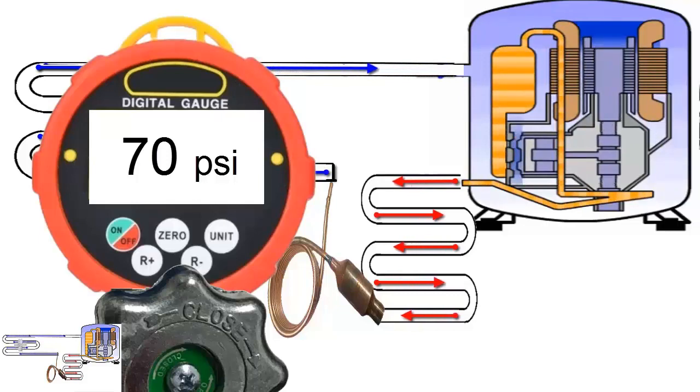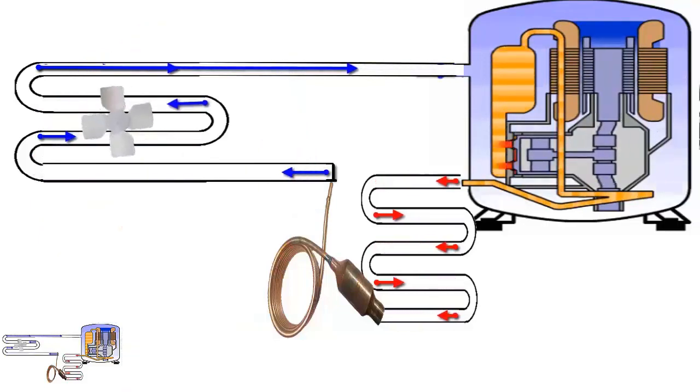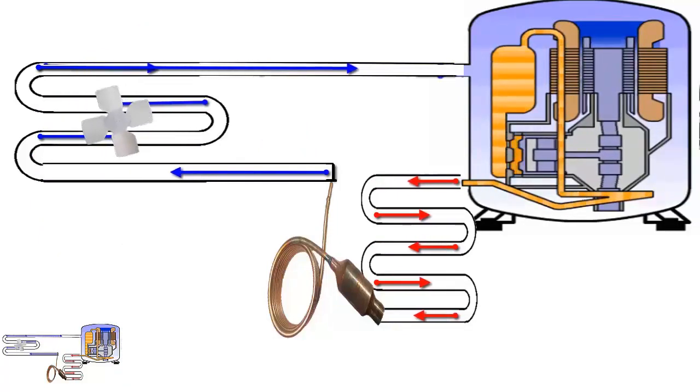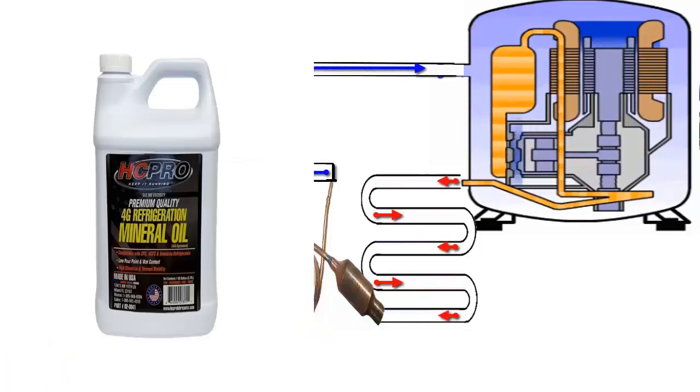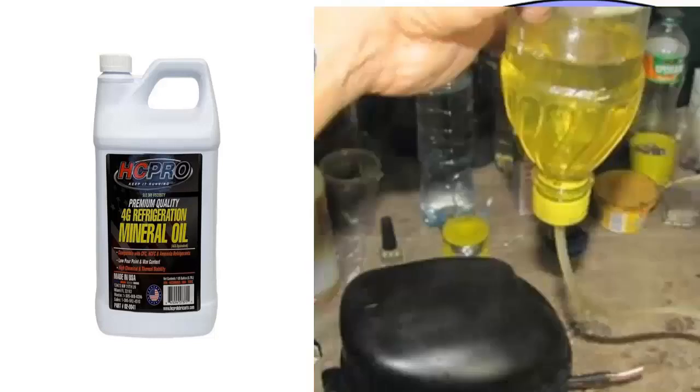R600A generally has very good miscibility with any type of lubricant. Due to the good solubility between mineral oils and these refrigerants, there are systems where it may be necessary to use oils of higher viscosity to compensate for this excess solubility.